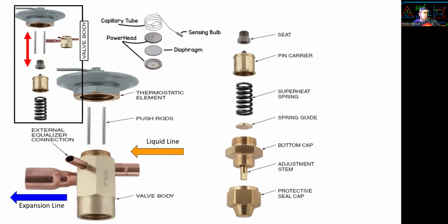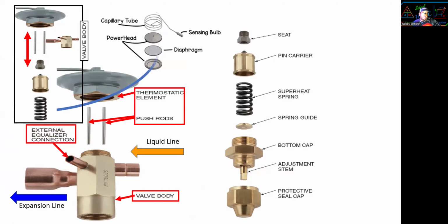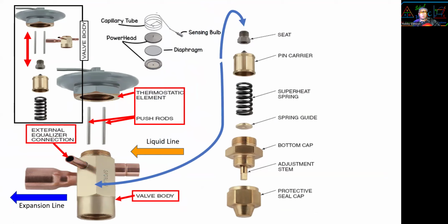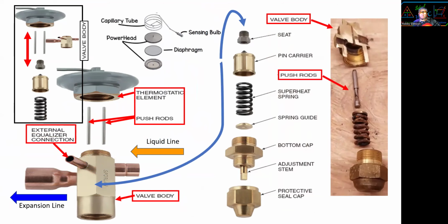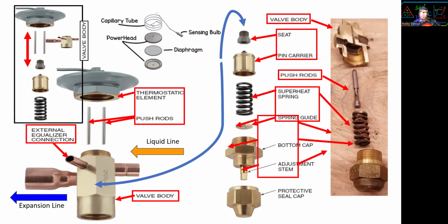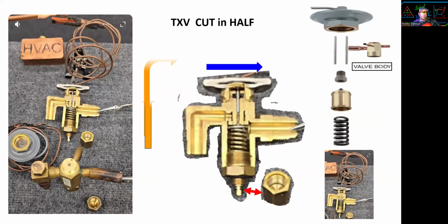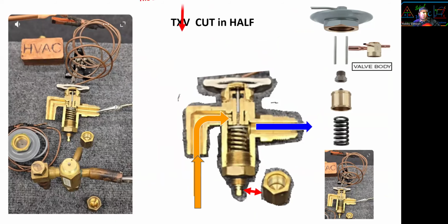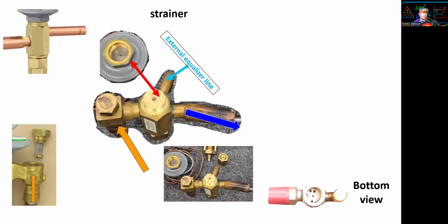Okay, now let's break apart the expansion valve. Liquid in, liquid out. There's the body, the thermostatic element or the head, and push rods. This is the external equalizer connection. Now all the stuff goes inside the body. We have this picture of the valve and the push rod, the seat and the pin carrier, superheat spring and spring guide, and the bottom cap adjustment screw and protective cap. All right, TXV cut in half, liquid in, the expansion out. The element head rod pushes the spring. Okay, next slide. This is the external equalizer over here, suction, liquid, the head goes over here.